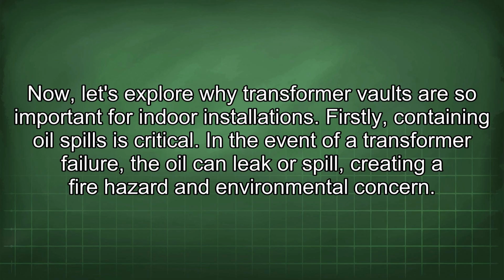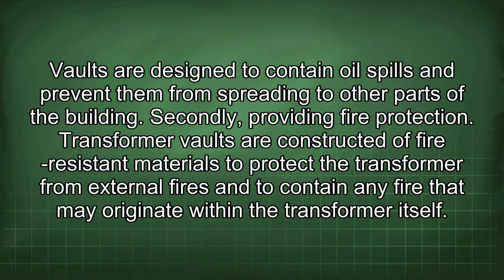Now, let's explore why transformer vaults are so important for indoor installations. Firstly, containing oil spills is critical. In the event of a transformer failure, the oil can leak or spill, creating a fire hazard and environmental concern. Vaults are designed to contain oil spills and prevent them from spreading to other parts of the building.